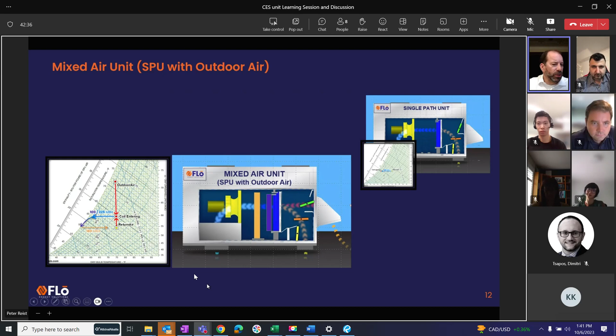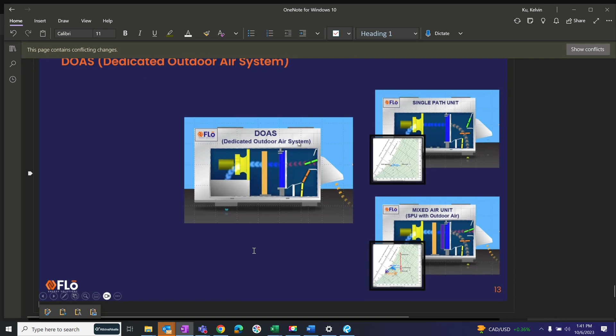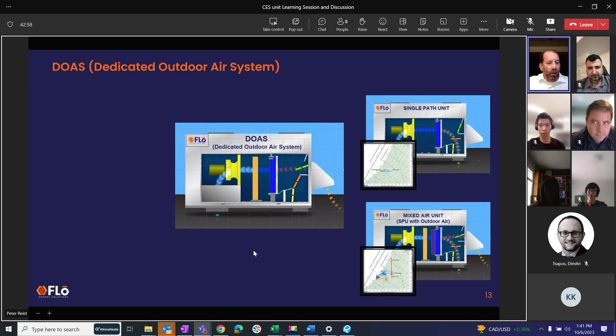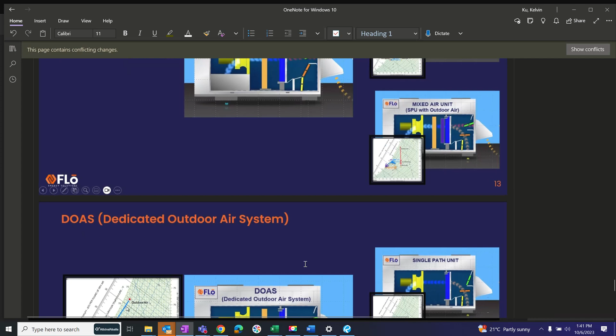Because of this lack of sufficiency, what the world did is they came up with these DOAS units, dedicated outdoor air systems. A DOAS unit takes the outside air, and only the outside air goes across the coil. The benefit of this is you have a relatively small amount of moisture that's spending a lot of time on usually a really big coil, by the way. These are usually like 6-row coils. And so you're really able to get the moisture out. When you look at the psychrometric chart of it, you see it makes sense. The outdoor air is just drawn right down along the saturation curve. Moisture is just pouring out of it. And then we add whatever reheat we need to bring it back up to a tempered temperature. So you can see this improvement and advantage that this thing has as a dehumidification system.